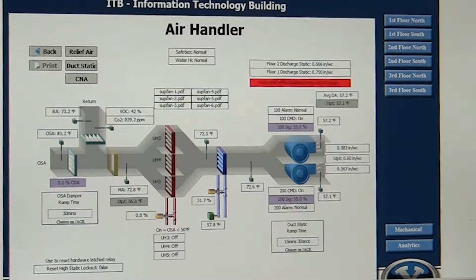So anyway, we have a window coming up this fall where if we've got 55, 60 degree air, we can put our air handlers in full outside air. We need to be careful how fast we go to outside air—you don't want to open it full up and overpressurize the building. So do it slowly.